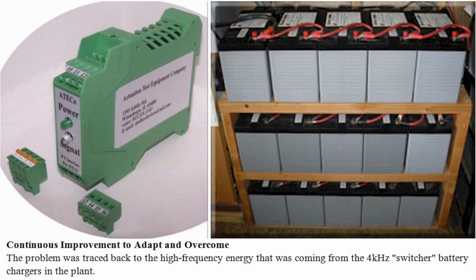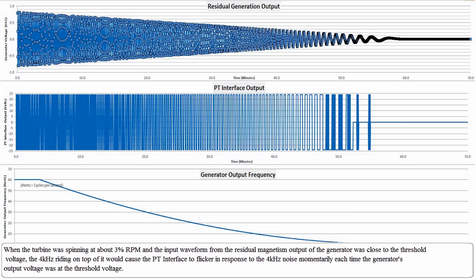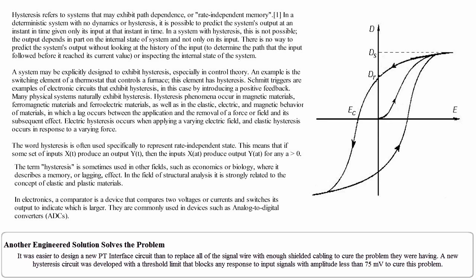The problem was traced back to the high-frequency energy that was coming from the 4 kHz switcher battery chargers in the plant. When the turbine was spinning at about 3% RPM and the input waveform from the residual magnetism output of the generator was close to the threshold voltage, the 4 kHz riding on top of it would cause the PT interface to flicker in response to the 4 kHz noise momentarily each time the generator's output voltage was at the threshold. It was easier to design a new PT interface circuit than to replace all of the signal wire with enough shielded cabling to cure the problem they were having.